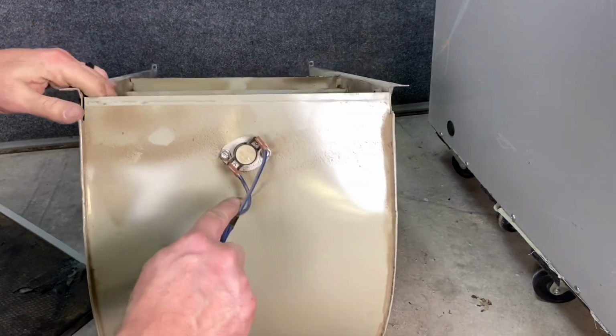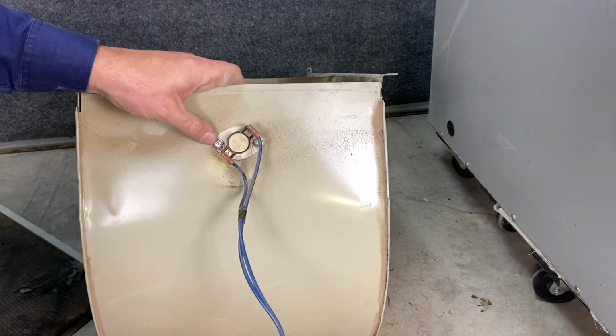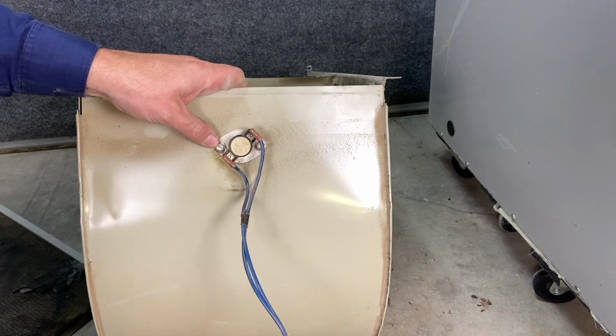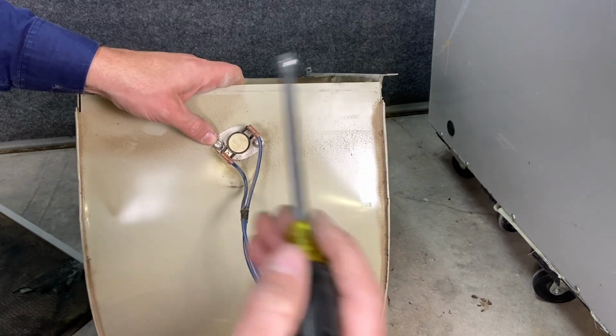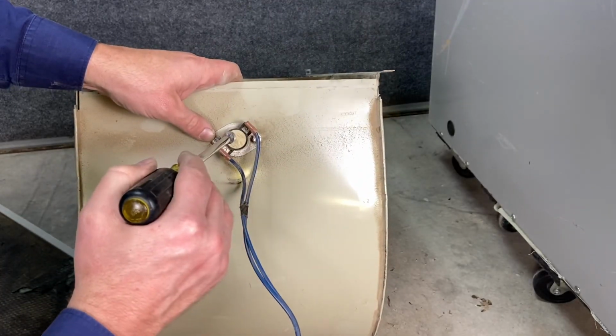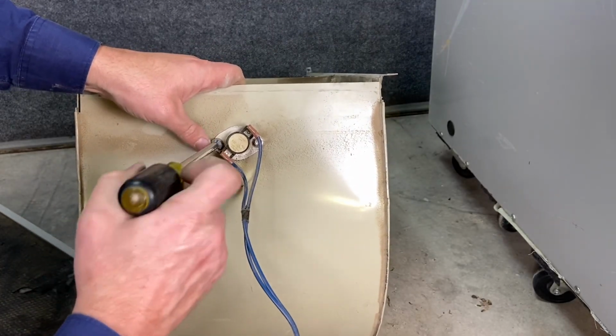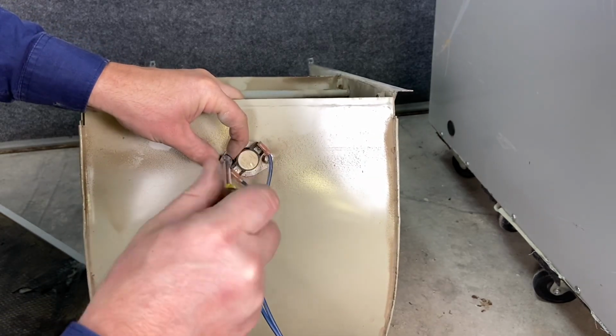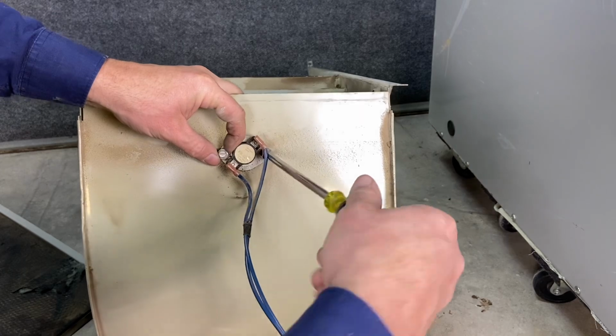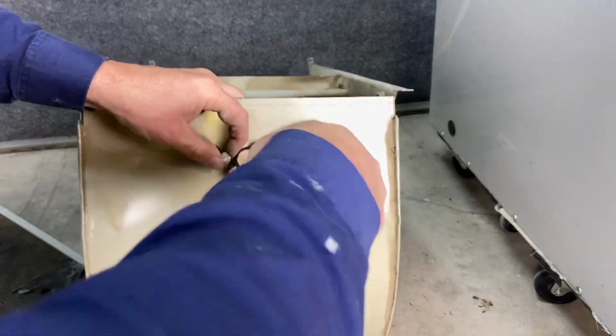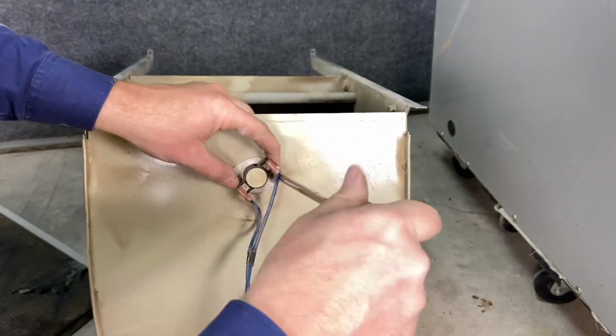This sensor is an auxiliary limit switch. It's going to protect it from overheating. So say this fan motor stopped working and the primary limit failed, the heat's going to keep building up until this one shuts off the unit. This one's going to be at a much, much lower temperature because it's much farther away from the heat exchanger. So we want this guy to shut off at a lower temperature point so we know we're protected if we have any safety issues.